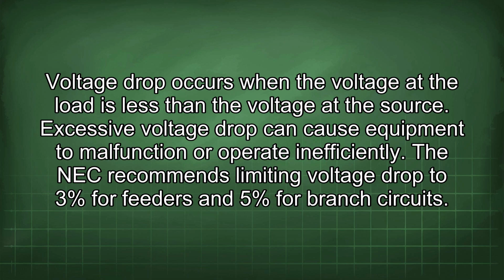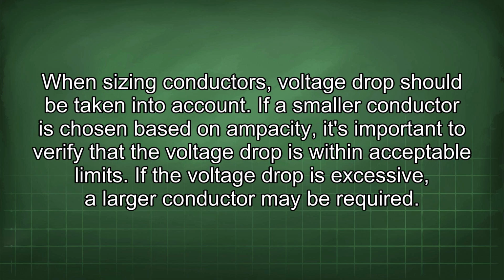Voltage drop occurs when the voltage at the load is less than the voltage at the source. Excessive voltage drop can cause equipment to malfunction or operate inefficiently. The NEC recommends limiting voltage drop to 3% for feeders and 5% for branch circuits. When sizing conductors, voltage drop should be taken into account. If a smaller conductor is chosen based on ampacity, it's important to verify that the voltage drop is within acceptable limits. If the voltage drop is excessive, a larger conductor may be required.